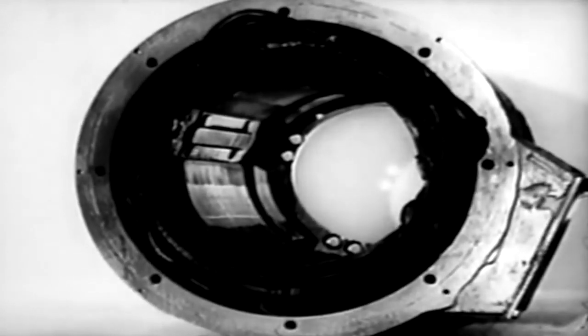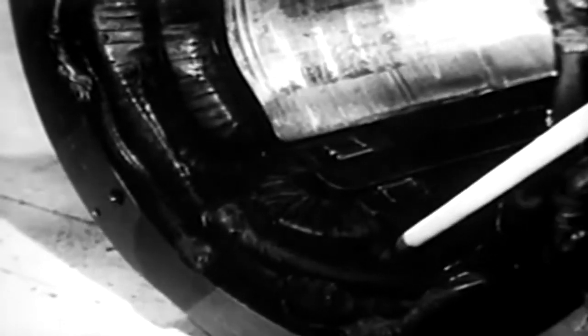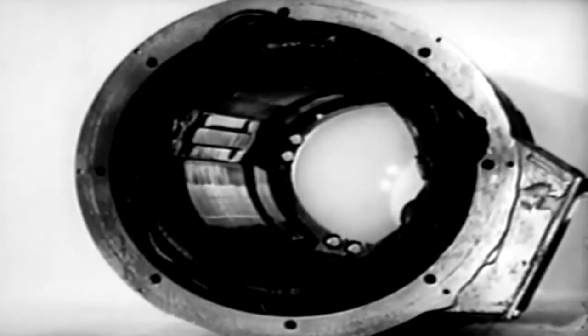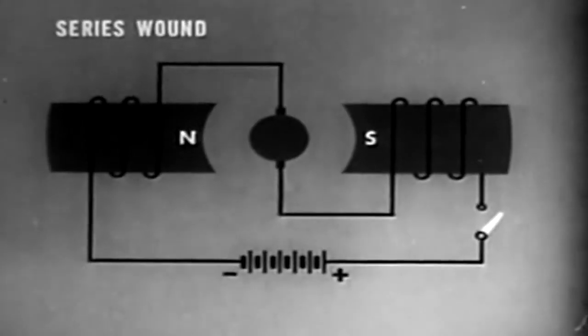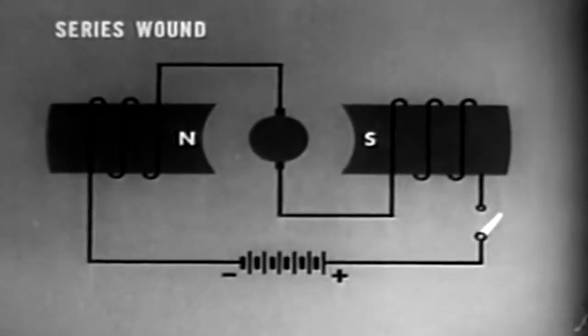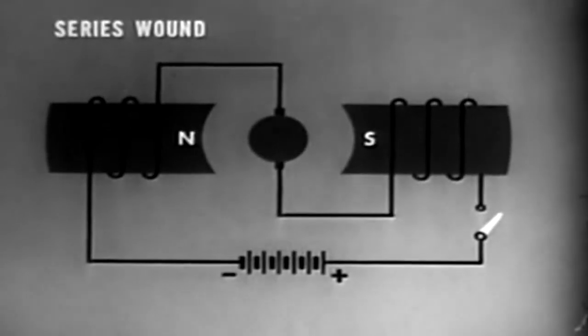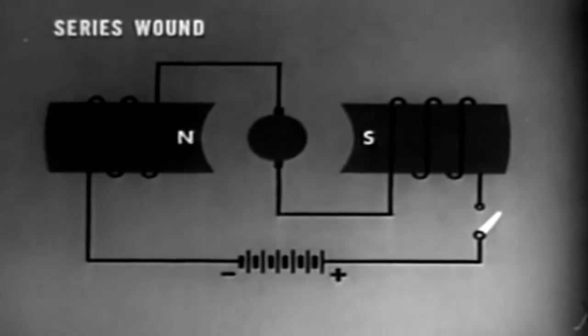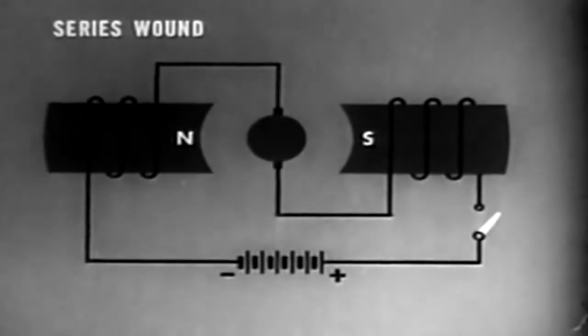Just as in DC generators, DC motors seldom use permanent magnets for the field — instead, electromagnets are used. Like with a DC generator, field windings are constructed in several ways, each type with special characteristics and specific uses. The series wound motor has good starting torque or turning force. Torque depends on armature current and on field strength. Since field strength is proportional to current, the high starting current before CEMF is developed affects torque as the square of the current.